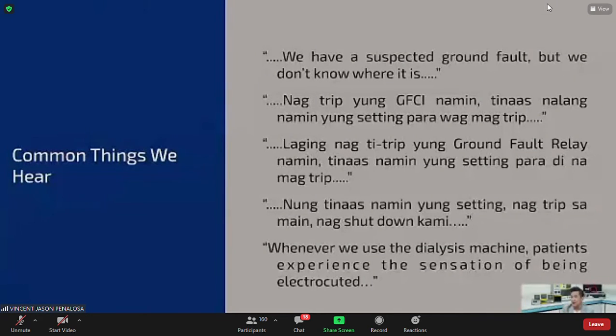First off, we have a suspected ground fault, but we don't know where it is. In Tagalog, nag-trip yung GFCI namin. GFCI is ground fault circuit interrupter. Nag-trip yung GFCI namin, tinaas na lang namin yung setting para wag mag-trip. Probably the worst thing you can do. Suddenly, you mess up your protection coordination. That requires a different topic altogether, a different study. Now, there's another one. Laging nagtitrip yung ground fault relay namin. Tinaas namin yung setting para di mag-trip. Again, another problem. And there is a follow-up there. Nung tinaas namin yung setting, nag-trip sa main, nag-shutdown kami. Of course, we don't do that.